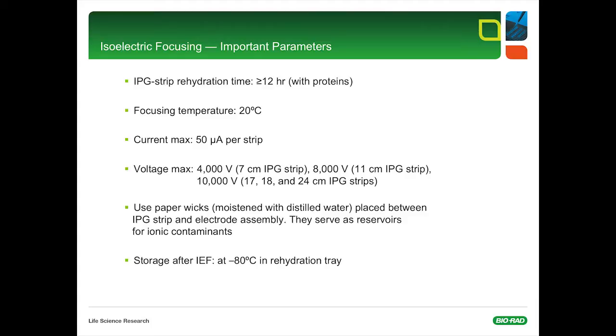Here is a summary of the most important parameters in IEF with IPG strips. IPG strip rehydration time is about 12 hours with proteins, 6 to 8 hours without proteins. Focusing temperature worldwide is always 20 degrees Celsius. The maximum current per strip is 50 microamps. Maximum voltage is strip length dependent. For example, 4,000 volts for 7 centimeter strips, 8,000 volts for 11 centimeter strips, and 10,000 volts for 17, 18, and 24 cm long IPG strips. Very important is the usage of paper wicks, moistened with distilled water, placed between the IPG strip and the electrode assembly. The paper wicks serve as a reservoir for ionic contaminants during isoelectric focusing. After the run, you can use your IPG strips right away or they can be stored at minus 80 degrees Celsius in the rehydration tray.